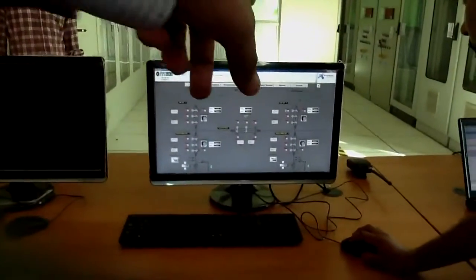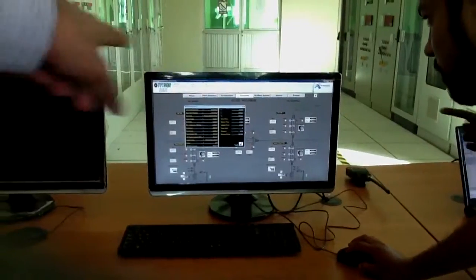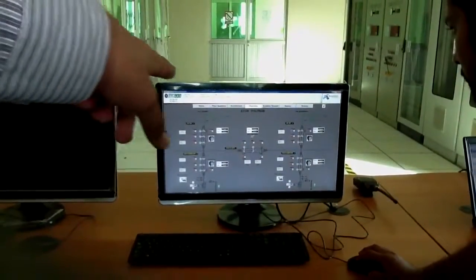Okay. And this is a SCADA system. You can monitor everything from here. You can check everything from the screen. This is our main SLD for maintenance and handover, and you can see all the 5 circuit breakers: the 2 incoming, for example line bay 2, line bay 1, the transformer bay, and the bus coupler.